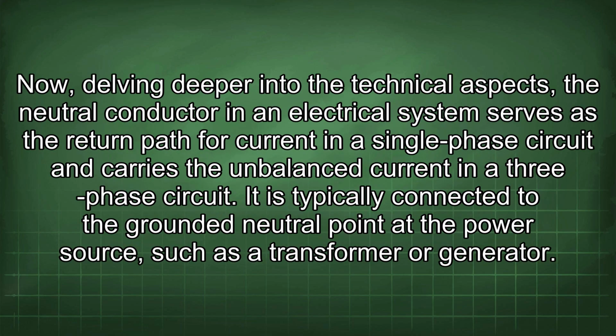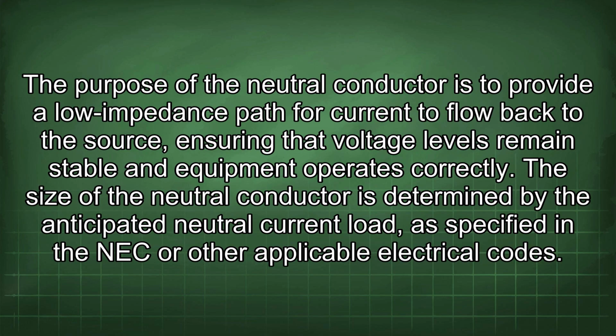Now, delving deeper into the technical aspects, the neutral conductor in an electrical system serves as the return path for current in a single-phase circuit and carries the unbalanced current in a three-phase circuit. It is typically connected to the grounded neutral point at the power source, such as a transformer or generator. The purpose of the neutral conductor is to provide a low impedance path for current to flow back to the source, ensuring that voltage levels remain stable and equipment operates correctly.